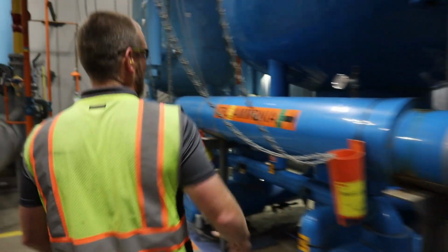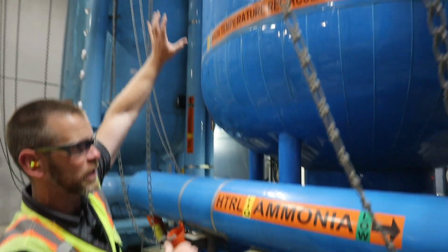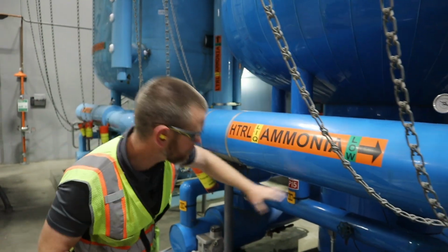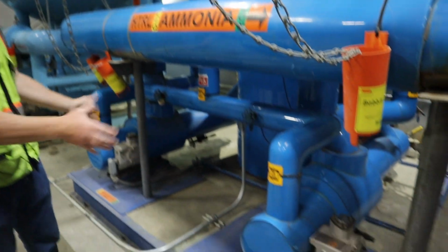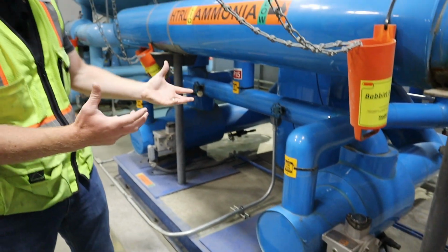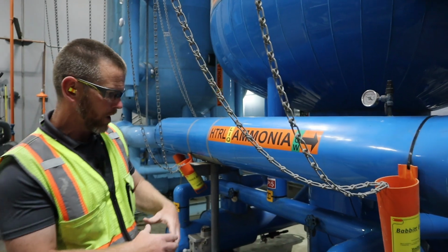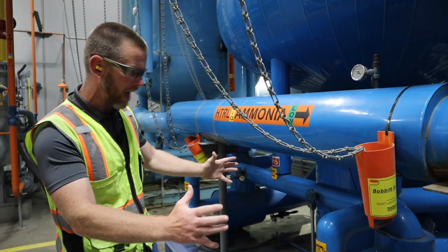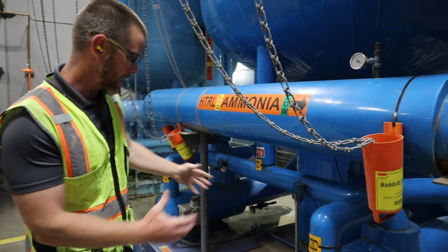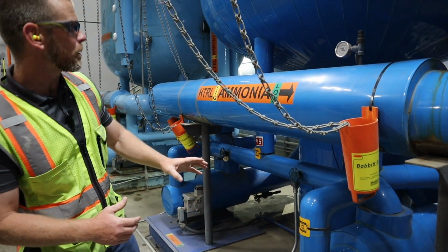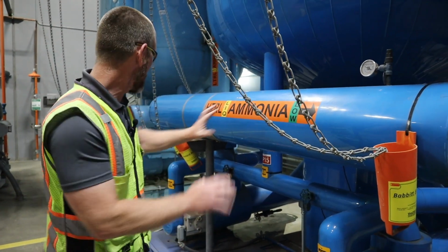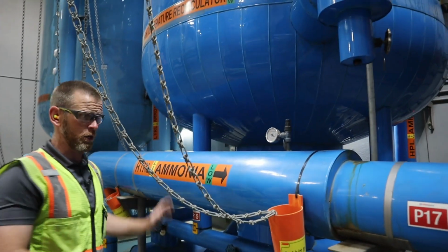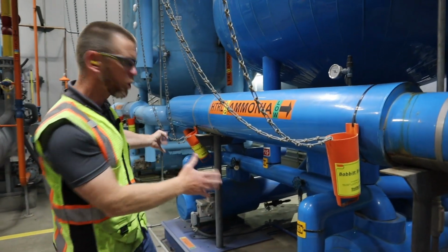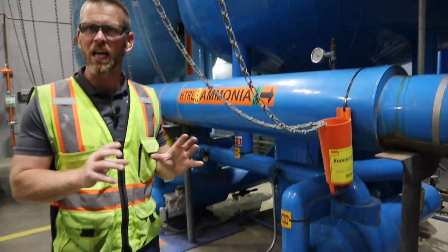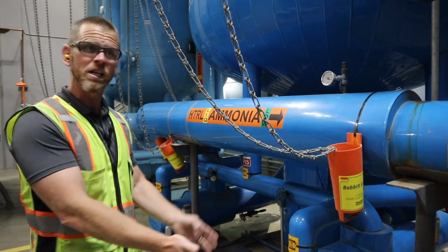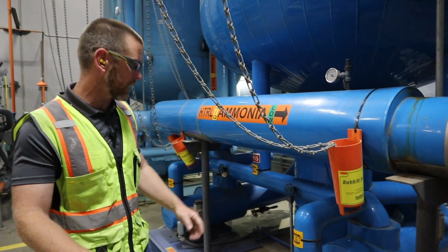From this vessel now, liquid obviously comes to the bottom, vapor to the top, which is supplied back to the compressors. It feeds these pumps, and there's two pumps. They're insulated, so you can't see the pumps super well, but these are hermetically sealed pumps. So there's less leak potential, there's no shaft seal where it can leak. Liquid is supplied to these pumps and then pumped out through this pipe, which they share, out to the evaporators, which are up on the roof. There's two pumps, and that's simply for redundancy, not because the two would run simultaneously. If one pump fails, the other will turn on. They can alternate back and forth, lead and lag.